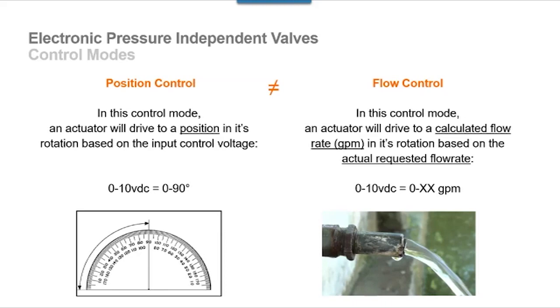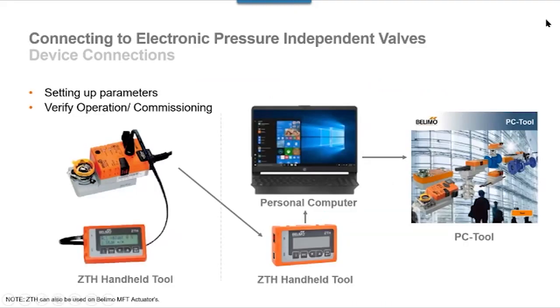Now, I mentioned before when we were talking about this, that we do have devices you can use to make adjustments in the field. For Belimo, we have a handheld device that, as you can see, plugs right into the actuator. I'll show you a couple of pictures of this in a couple of slides. But there's also the capability of doing software on your laptop with the Belimo PC tool. Frankly, for what you're doing out in the field, the ZTH will show you the flow from the flow meter. The ZTH will allow you to change the flow. It will allow you to toggle between pressure independent and pressure dependent mode. And I'll show you why you might want to do that in a moment. But the bottom line is, the majority of what you can do is with that handheld tool.